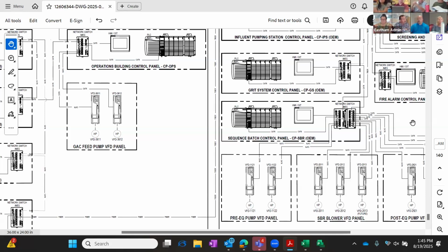Are any of these servers critical to the operation of the plant, because of catastrophic failure? That's what I'm really driving at. In other words, is this system operating the plant, and is there a single point of failure that could cause a catastrophic issue?